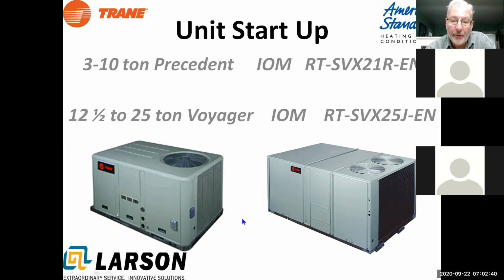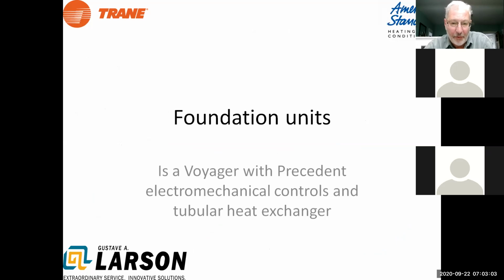There are some new controls that are being introduced right now. I don't have any information on them as of yet, but I will as they're released. We'll make sure you guys get all that information. And then the Voyagers are 12.5 through 25 ton, and that is basically just Reliatel at this point. We also have another model called Foundation, and Foundation is our 12.5 through 25 ton models that are pretty basic, pretty simple. It's like a Voyager with Precedent electromechanical controls. Doesn't have anything fancy on it, just basic transformer, contactors, ignition board, nothing fancy about them at all. They also come with tubular heat exchangers.